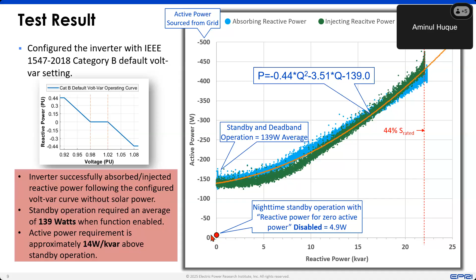It's not a perfect linear curve, but we have seen roughly, again, a similar 14 watt per kVAR. We cannot generalize that this will be the case for all inverters, but for the 2 inverters that we have tested, just to keep it on there's a different magnitude of active power needed. But for the VAR, we have seen roughly 14 watt per kVAR for both of the inverters that we tested. So far, that's the individual inverter performance from our lab testing.